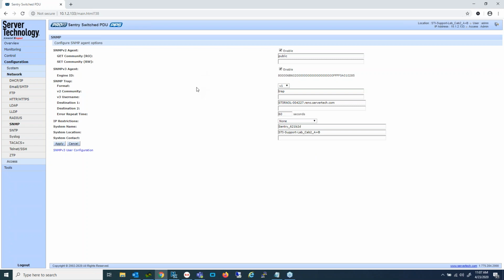The basics with SNMP are that, similar to syslog, you have up to 2 destinations you can define, destination 1 and destination 2. I've already defined a destination, which is my laptop here at my home office. Also note that out of the box, the PDUs default to both SNMP v2 and v3 being disabled. I've already enabled them because it takes a couple minutes after enabling to perform a restart, so it's pre-enabled at this point, and I'm going to demonstrate using SNMP version 2.